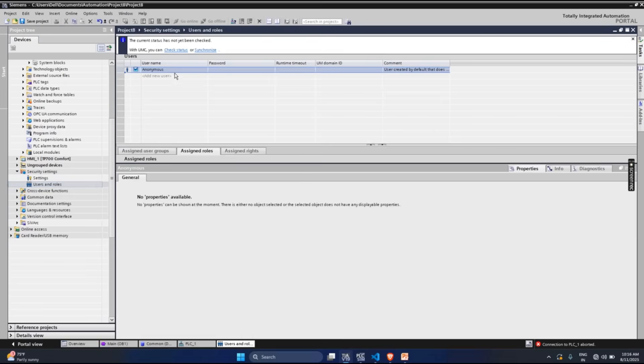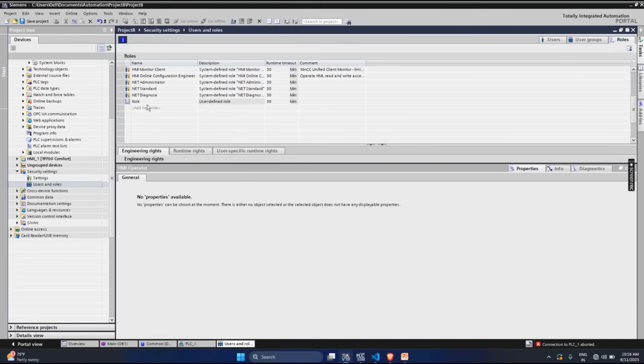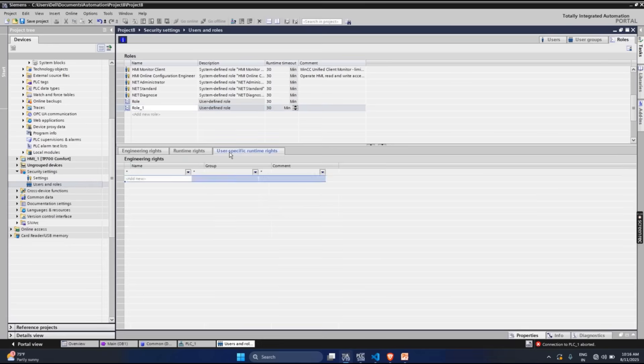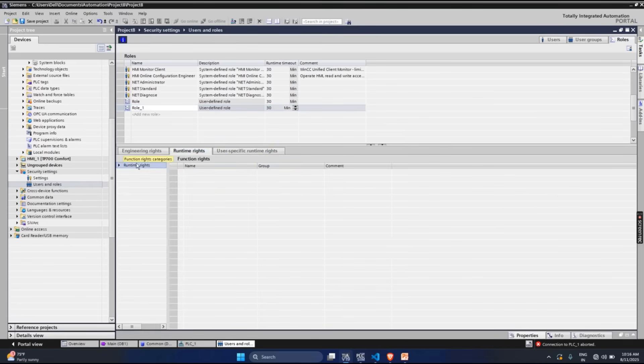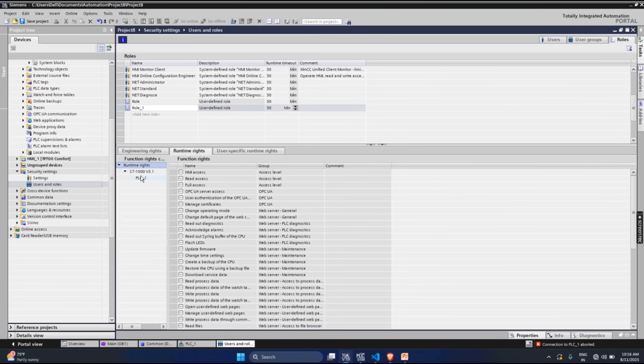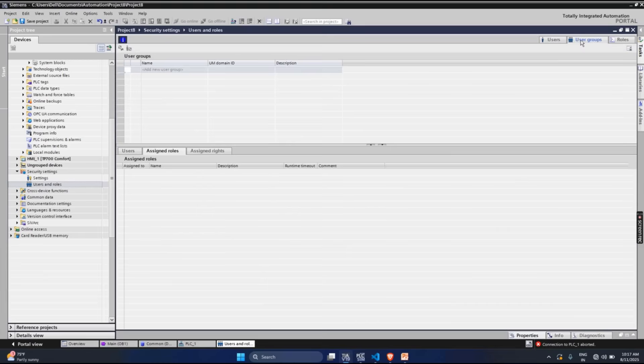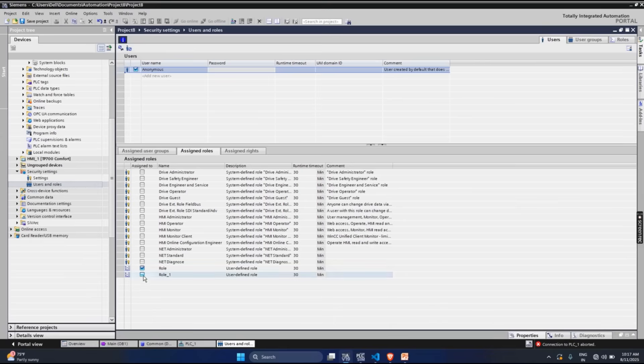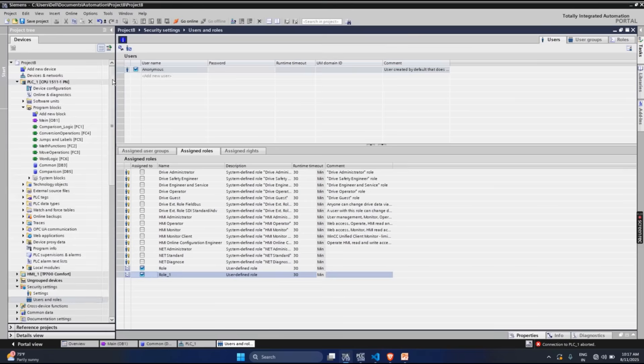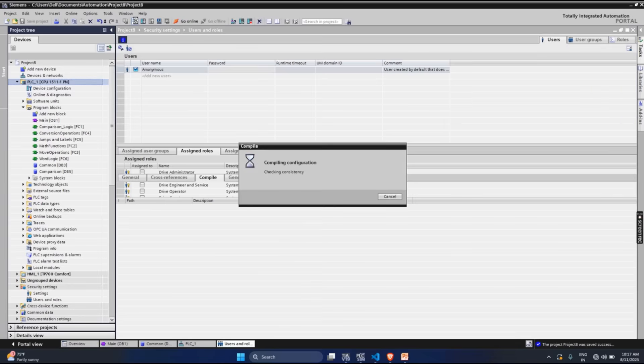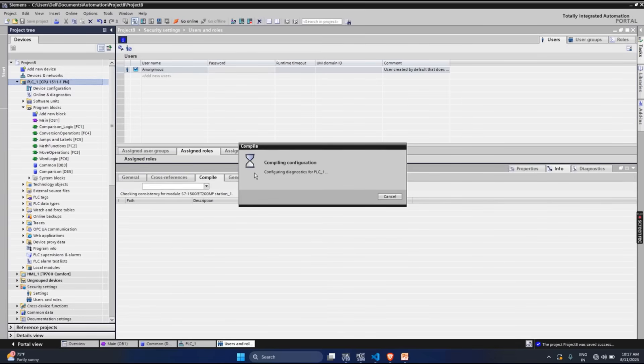Go to users and roles. By default you will have an anonymous user. You need to go to the roles section and add a new role. With this role, go to user specification, runtime rights, select this user, select your PLC, and select full access. After saving this, with the anonymous user you can just click the tick here. Then compile — save and compile your project once — and after compiling, the get/put option will be available for you to enable.